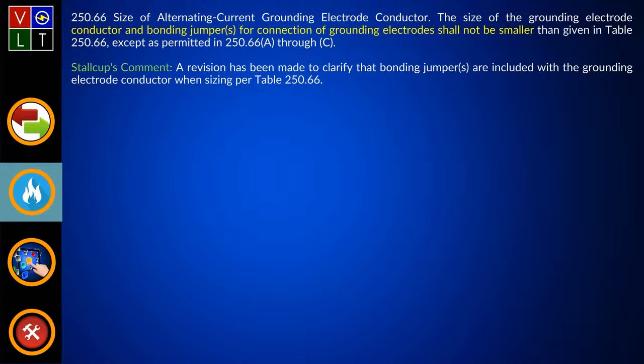What it says is the size of the grounding, this is for 250.66, as far as including it with the sizing for table 250.66. The size of the grounding electrode conductor and bonding jumper or jumpers for connection of grounding electrodes shall not be smaller than given in table 250.66. So if I'm sizing for my bonding jumpers or my grounding electrode conductors, it tells you to use the table. And then it says, once again, except as permitted in 250.66A through C.